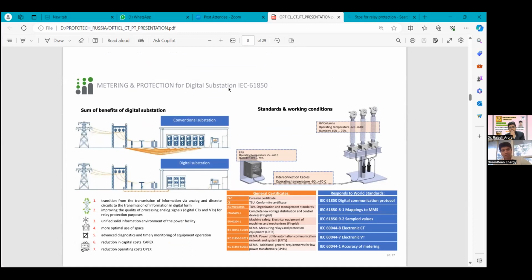Metering and protection for digital substation as per IEC 61850. This picture shows the conventional substation, wherein you have to lay a number of cables, and the panels are also more in comparison to the digital substation. So here there are 6 panels in comparison to only 3 panels, and a number of cables you can remove. Single fiber optic.